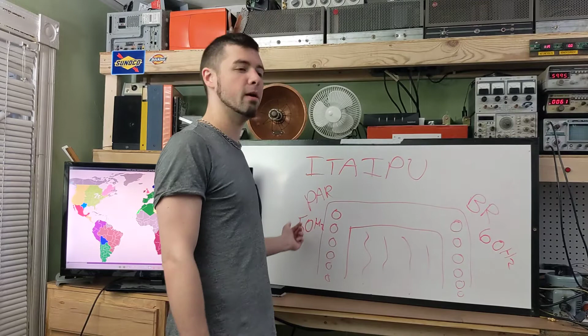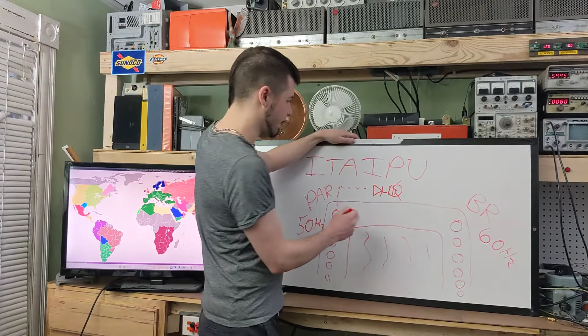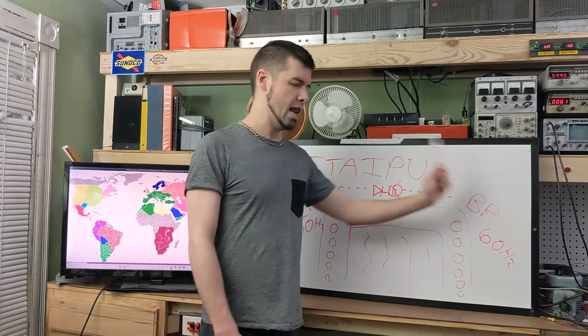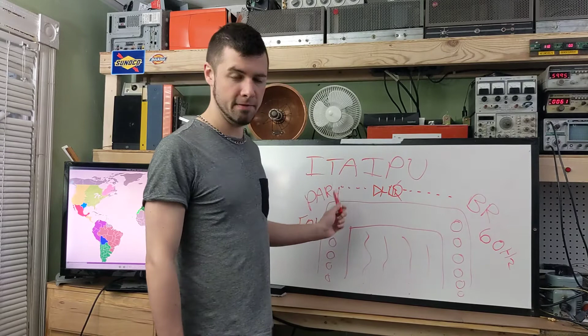So somewhere above the dam there's a converter station, and they convert 50 hertz power from the Paraguay side of Itaipu into 60 hertz power and sell it to Brazil. Interesting, right? When they built this, they didn't just decide Paraguay only needs, say, 3 gigawatts, so we'll only install that many 50 hertz generators and make the rest 60 hertz. Instead they split it evenly - 10 at 50 hertz, 10 at 60 hertz - and whatever Paraguay can't use gets converted to DC and then to 60 hertz so Brazil can buy it. I believe they also have the ability to sell some of the 50 hertz power into Argentina, which is also a 50 hertz country.